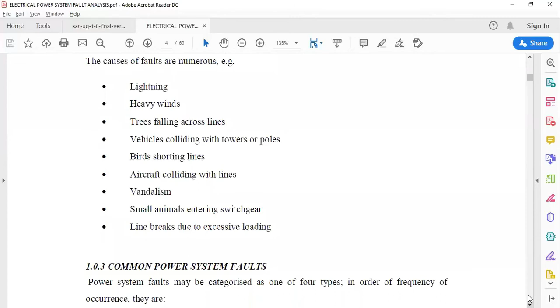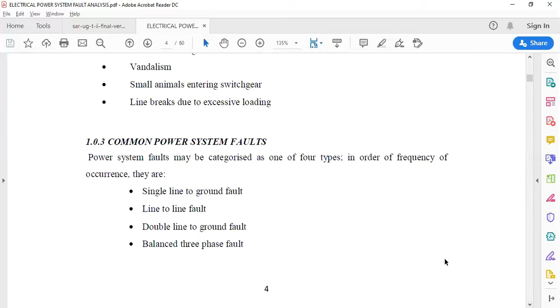Let's see the frequency of occurrence. Most of the faults in the power system are of the unsymmetrical type. In the unsymmetrical type, the frequency of occurrence of single line to ground fault is about 70%. Then comes line to line fault, then double line to ground fault, and very rarely a balanced three-phase fault occurs in the power system.